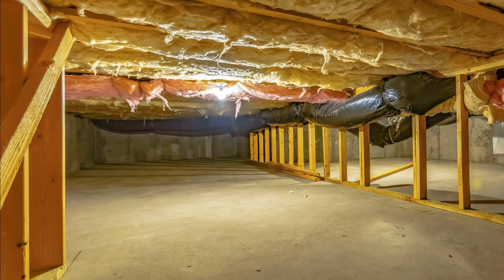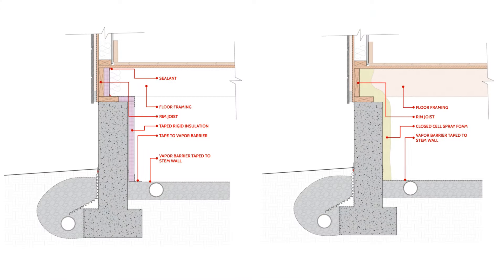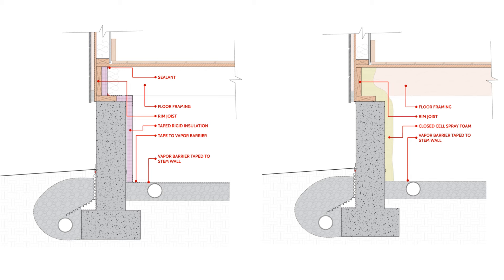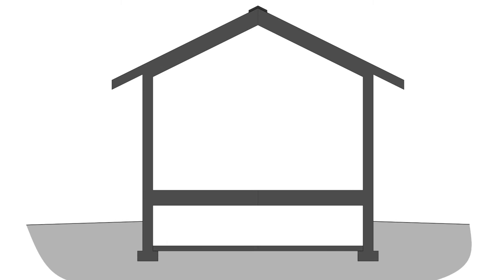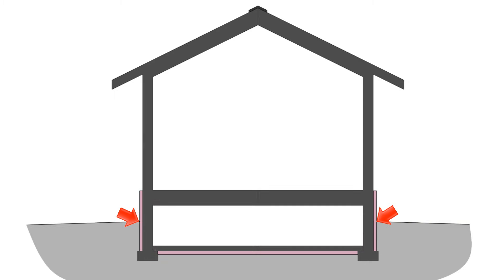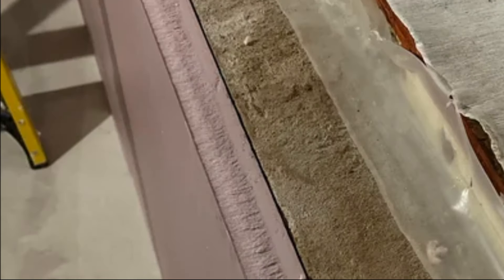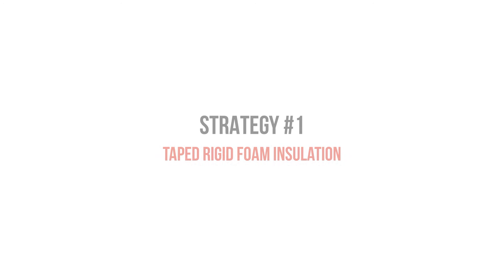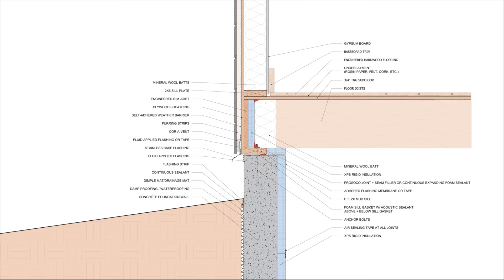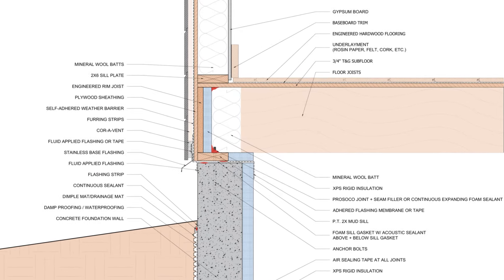Since a conditioned crawl space is essentially a short basement, we can use the same strategies to insulate it as we would a typical basement — either on the interior or on the exterior of the assembly, though insulating on the interior tends to be the most common strategy. The first strategy is to install taped rigid foam insulation on the interior side of the stem walls and around the rim joists, sealing the connection to the rim joists with a fluid-applied joint and seam filler compound or expanding foam sealant.